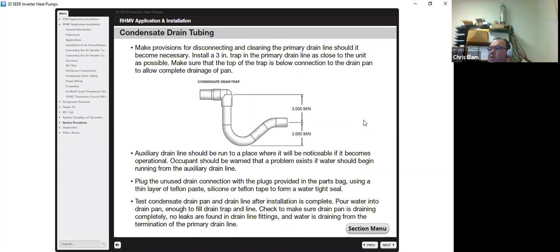Also, the auxiliary drain line should be run to a place where it will be noticeable if it becomes operational. Occupants should be warned that a problem exists if water starts to flow from the auxiliary drain pan. It's also important that you plug any unused drain connections with the provided plugs. Everything you need will be in the parts bag. Use a thin layer of Teflon paste, silicone, or Teflon tape to form a water seal.